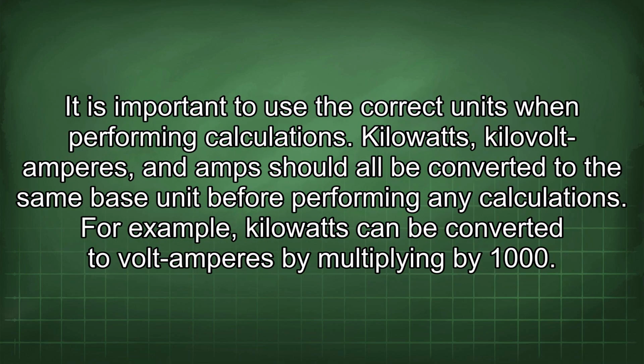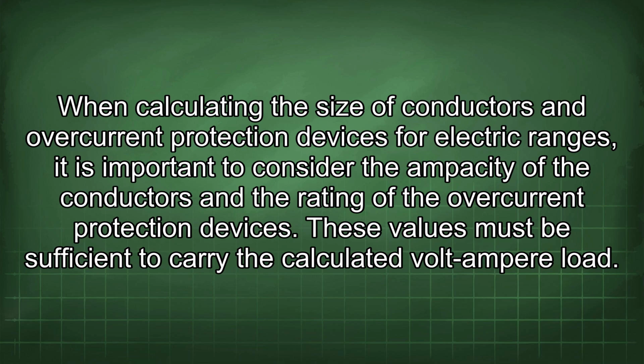It is important to use the correct units when performing calculations. Kilowatts, kilovolt amperes, and amps should all be converted to the same base unit before performing any calculations. For example, kilowatts can be converted to volt-amperes by multiplying by 1000. When calculating the size of conductors and overcurrent protection devices for electric ranges, it is important to consider the ampacity of the conductors and the rating of the overcurrent protection devices. These values must be sufficient to carry the calculated volt-ampere load.